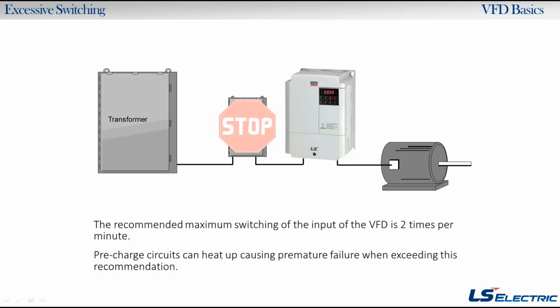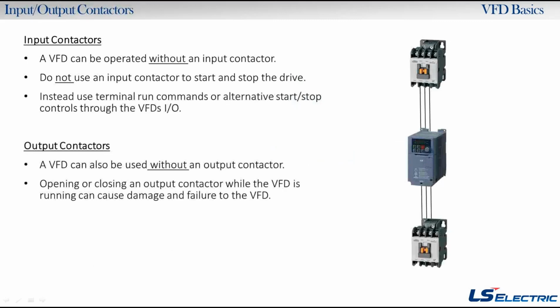So this one is also kind of similar: input contactors. Some guys will retrofit a drive in place of a soft starter or some kind of motor starter, and they'll leave the contactors there, okay? That's okay, but you really don't need an input contactor on the front end of the drive, because you should just be starting and stopping the drive with the I/O. So that's the P1 and the P2 terminals we mentioned before, forward and reverse. You should be starting the drive with something like that, or hitting the run on the keypad. Because if you're turning this drive on and off, it goes back to that previous slide where you're overworking that soft charge circuit.